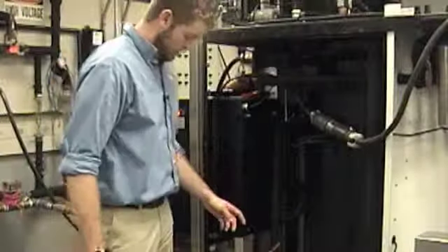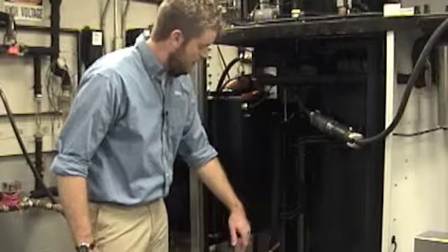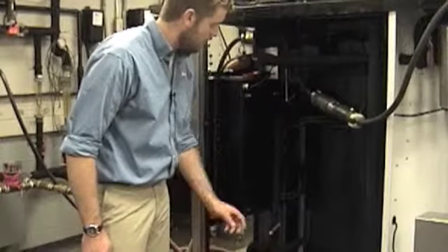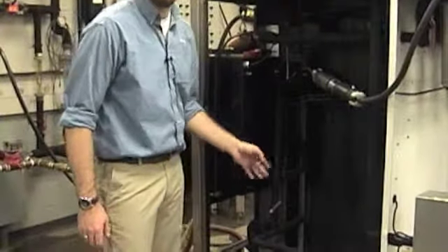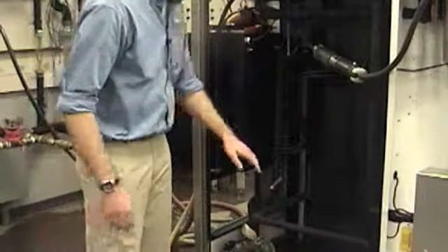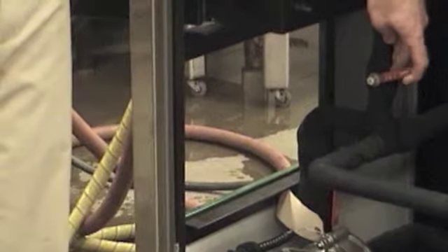It's important at this point to highlight the bypass valve. Right here, when you receive the unit, it's going to be wide open. Obviously, when you plumb everything up and hook it up, you're going to want to close it to make sure water's circulating through the loop out to the fountains. But you can also sort of control the amps and the pressure in your loop with this bypass valve. So right now we're going to go over to the electrical box. After this unit's been running for about 10 or 15 minutes, we're going to check our amps on all our different components.